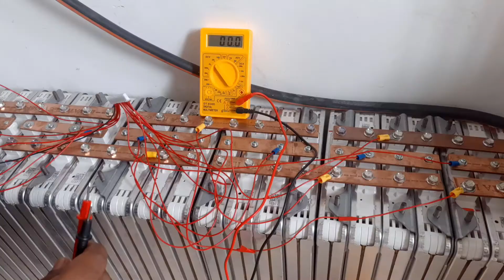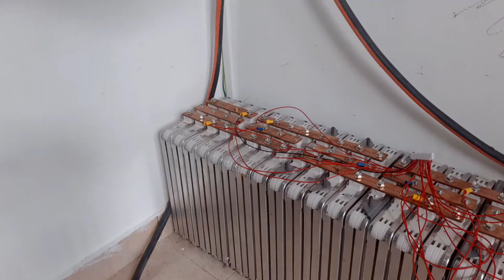Before you connect to the BMS, you have to cross-check that the connections are proper and correct by checking the voltage. So you have to start from your black first node and check the voltage for 4, 8, 12, 16, 20, 24, 28, 32, 36, 40, 44, 48, 52 and 56.9. It is confirmed that all are in the increasing order and are properly connected.